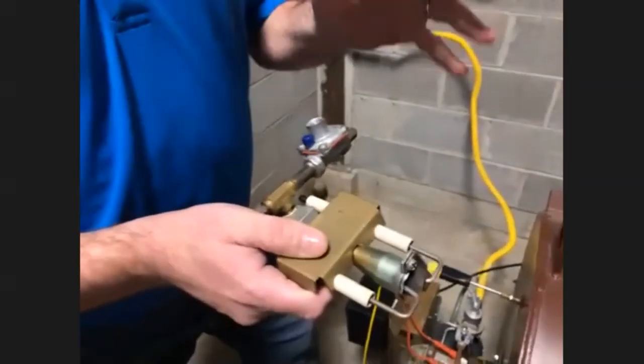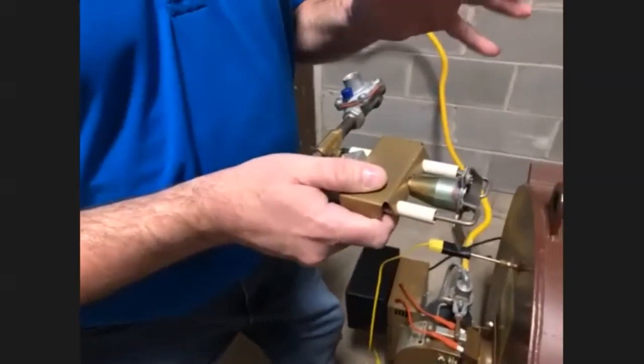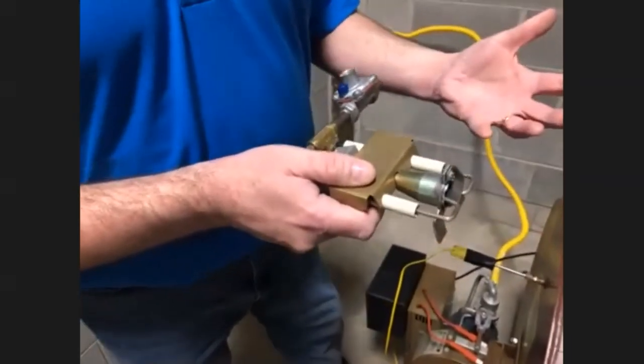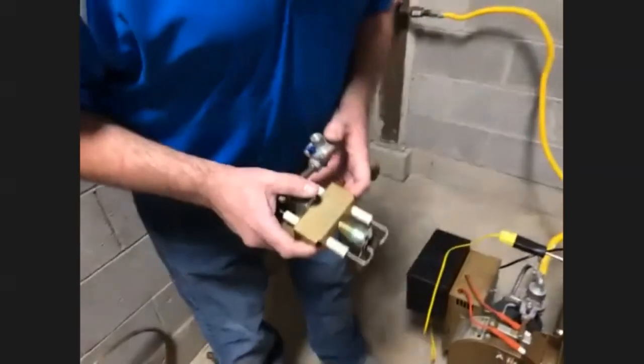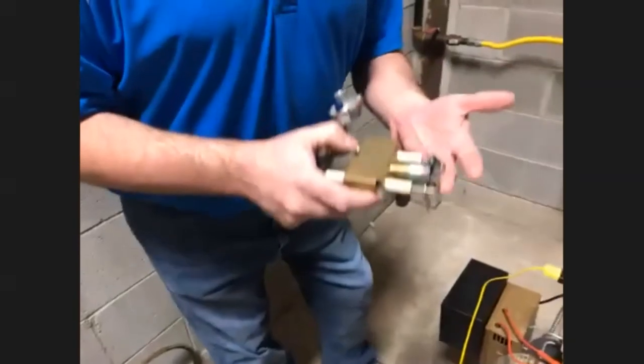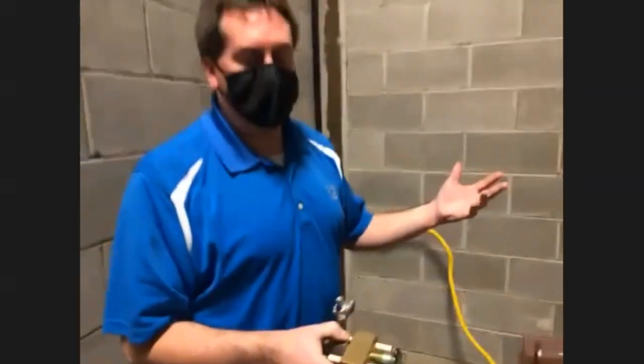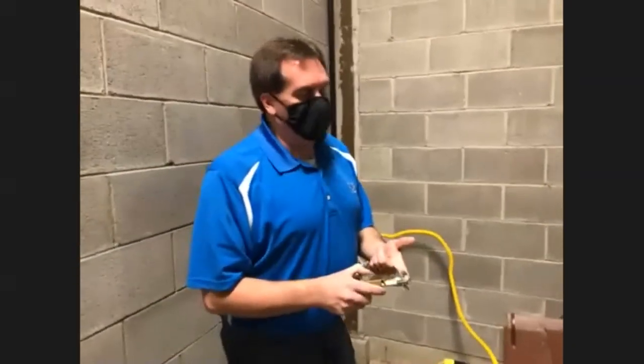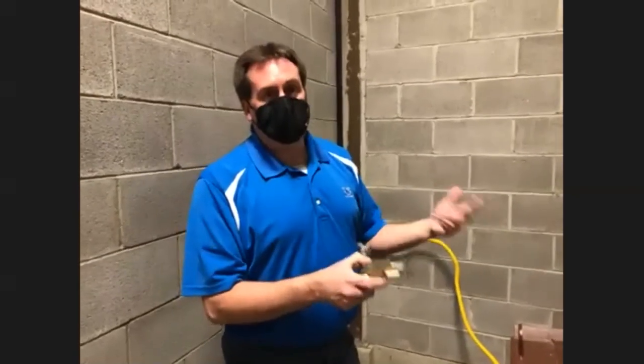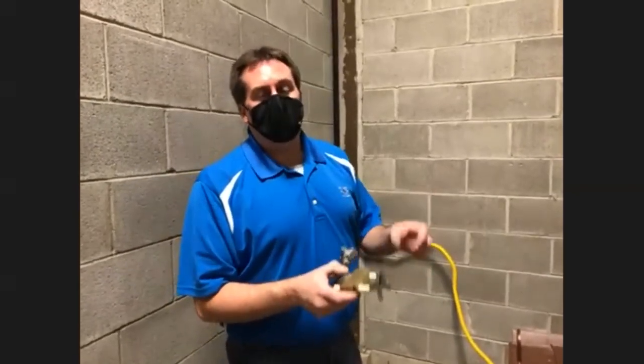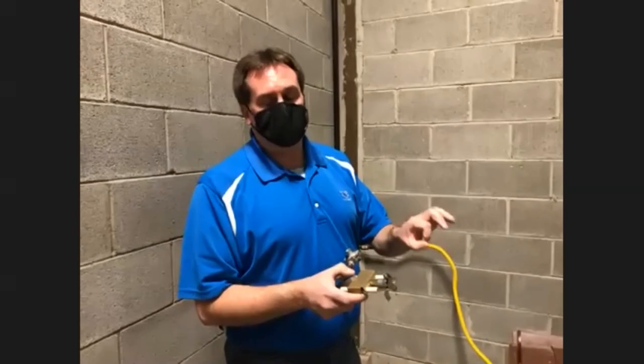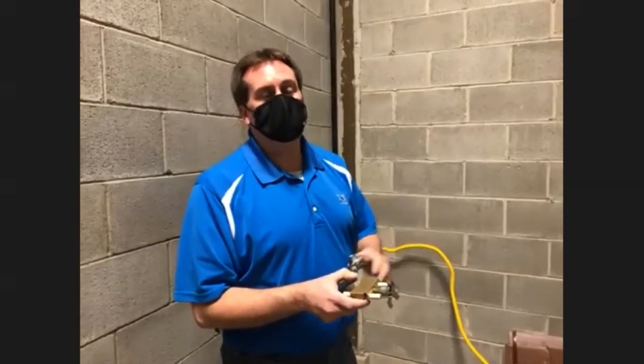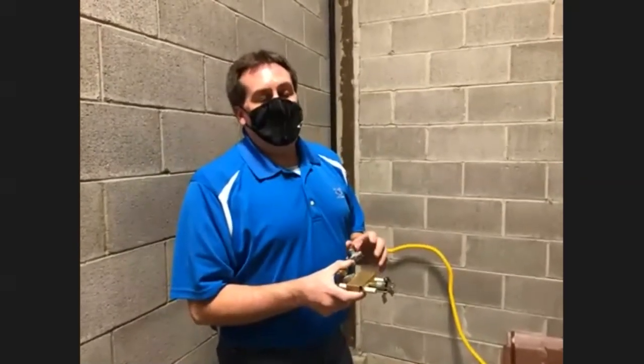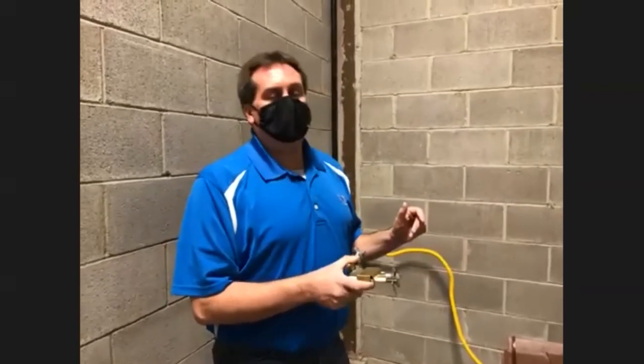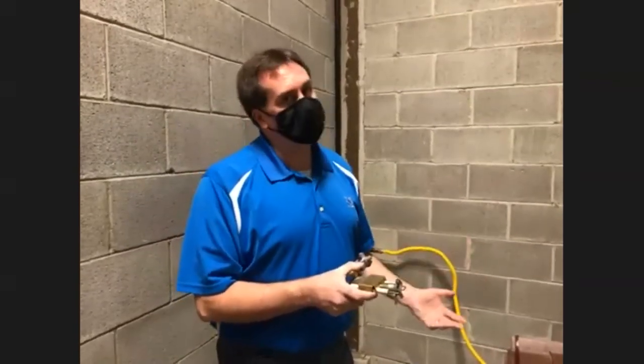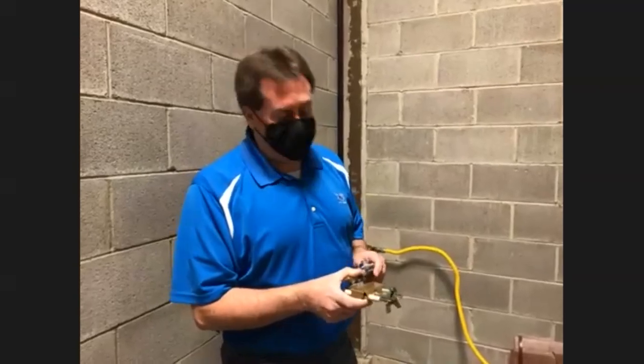If you are getting spark, but you're not getting any ignition or combustion, you may have a fuel problem. With that, you want to verify that your fuel supply is flowing properly and you have a proper supply. If you're using propane, verify your tank is full and you have the proper size plumbing going to your tank or to your cremator. And if all that is proper, maybe you're not getting the right pressure going through the cremator itself.